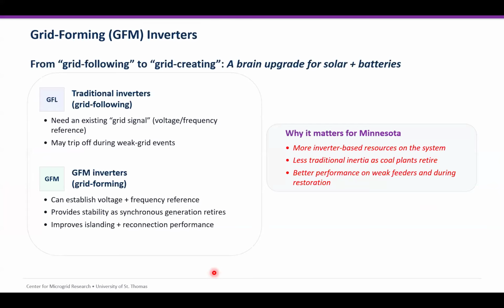Grid forming inverter. We have two expressions: grid following and grid forming. The grid following inverter is the one that exists in most of the inverters now. They just follow the grid. A grid creating or grid forming inverter is basically adding a brain to the inverter.